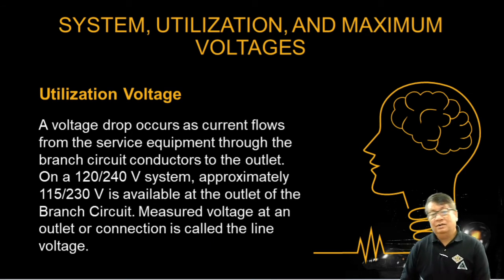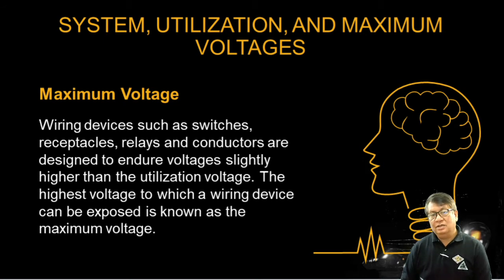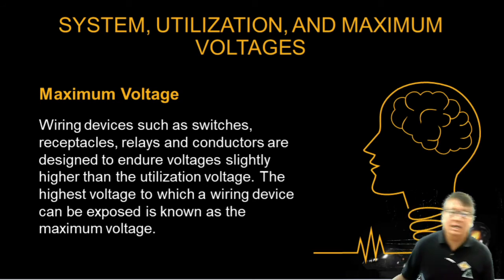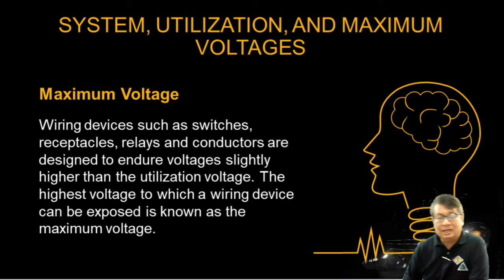We have also this utilization voltage. The voltage drop occurs as current flows from the service equipment through the branch circuit conductors to the outlet. Maximum voltage: wiring devices such as switches, receptacles, relays, and conductors are designed to endure voltages slightly higher than the utilization voltage. The highest voltage to which a wiring device can be exposed is known as maximum voltage. Yun po ang pinakataas na voltahe sa system. Otherwise, pag madagdagan pa yan, of course, it will damage our system, kasi masyado nang malaki ang ating mga voltahe.